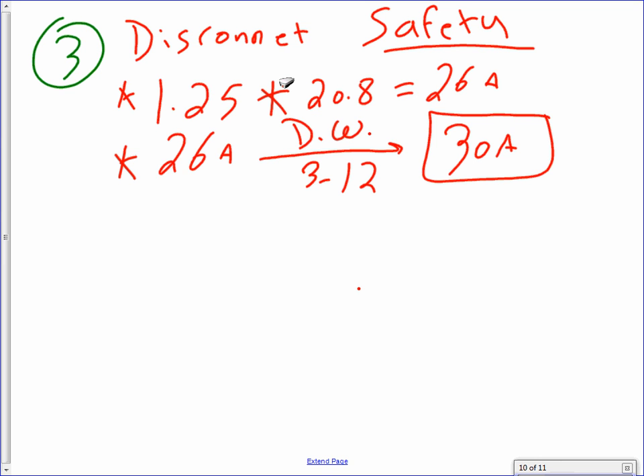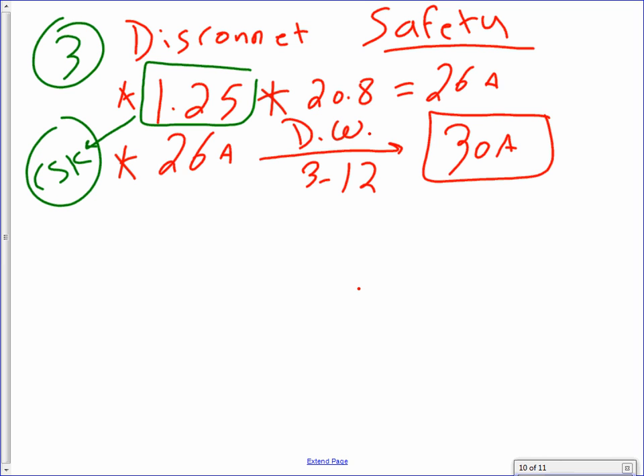So where would you get that multiplier? You're going to hear the CSK a lot. These are my initials. That's how we would do it. I size it like the conductors. That's how we size the conductor. So you need the disconnect to be able to disconnect the full load current. The full load current is 20.8. The next standard disconnect anyway is 30. But I like to use the continuous load, the same as we size a conductor, 1.25.